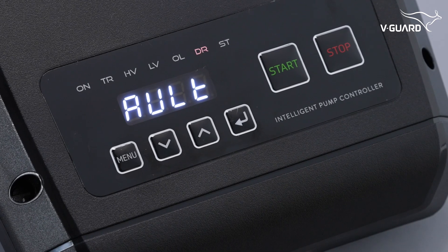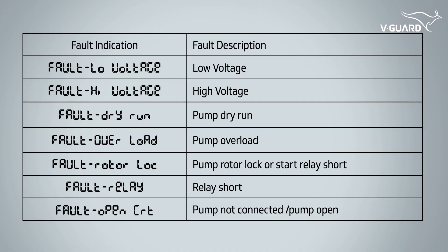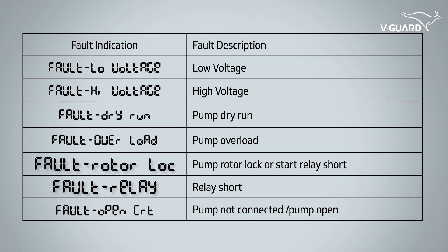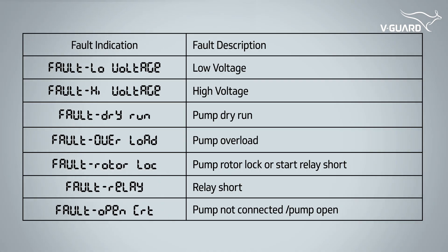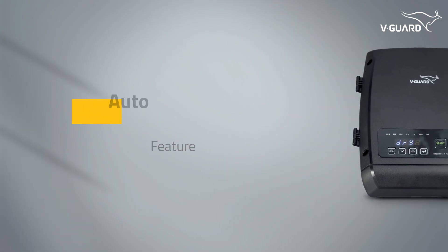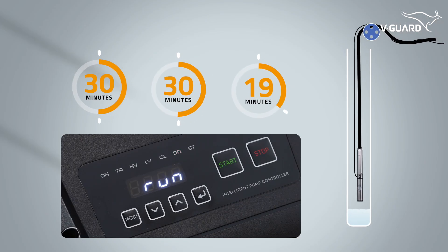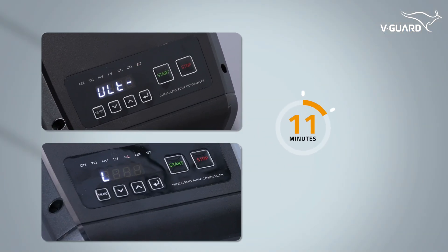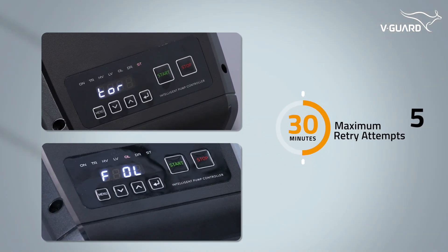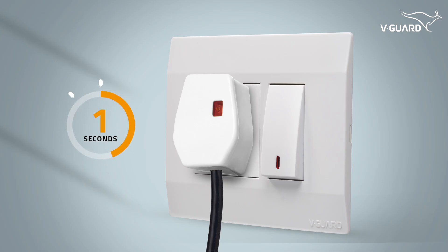The fault indication lights on the intelligent pump controller will help you identify and resolve issues quickly. Use the fault indications and their descriptions to diagnose and address faults effectively. The auto-retry feature helps recover from faults without manual intervention, reducing downtime. For dry run protection, the intelligent pump controller attempts to restart the pump after 30 minutes, up to 3 times. For other types of faults, the retry time is 30 minutes with a maximum of 5 retry attempts. If all retry attempts fail, manually reset the pump by turning off the main power supply for 1 second, then switching it back on.